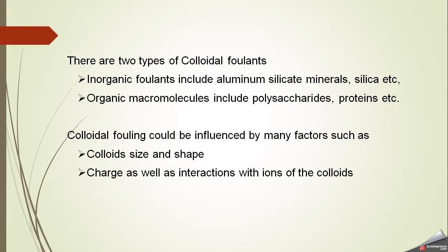There are two types of colloidal foulants: inorganic foulants, which include aluminium silicate, minerals, and silica; and organic macromolecules, which include polysaccharides and proteins. Colloidal fouling is influenced by many factors such as colloid size, shape, and charge, as well as interactions with ions on the colloids. Since colloids carry a partial charge, they can bond with each other and bind to the membrane surface.